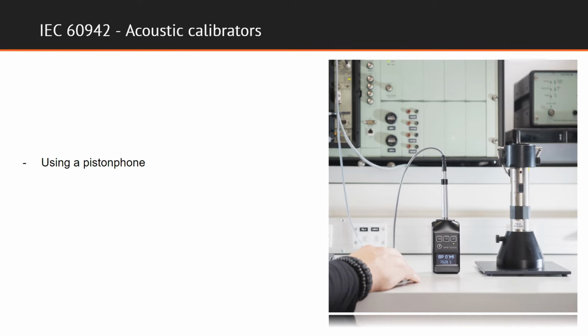Calibration is performed by performing the comparison method using a reference pistonphone as the standard comparative sound pressure level. The report for calibration of a level calibrator includes measurement of sound pressure level, frequency, and total distortion. If the instrument is equipped with an accessory barometer, this is checked at the current air pressure.